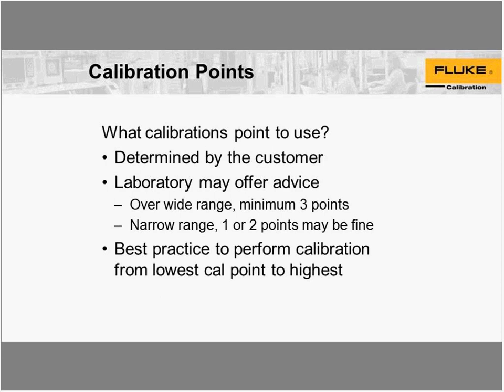Over a narrow usage range, one or two points may be fine. Consider a local warehouse food court with a Fluke 62 that measures pizzas as they come out of a pizza oven — that may be a situation where they have a very narrow usage range and one or two points may be sufficient. When considering calibration point order, you want to perform calibrations from the lowest point to the highest. If you do the highest point first, you'll heat up the body of the infrared thermometer, and when you go down to measure a low point, that reference temperature will be distorted and cause error in that measurement.